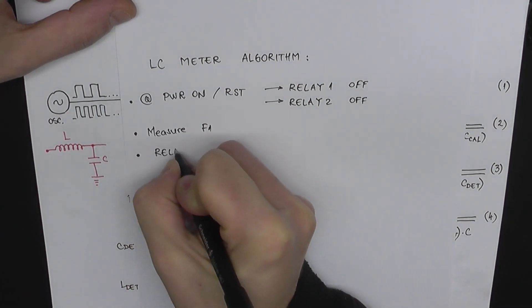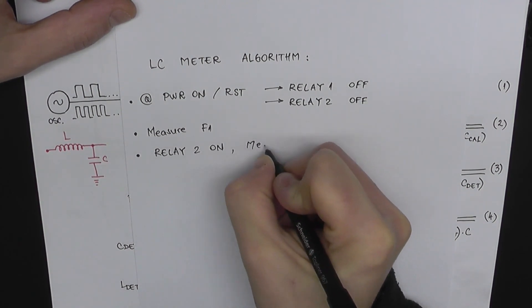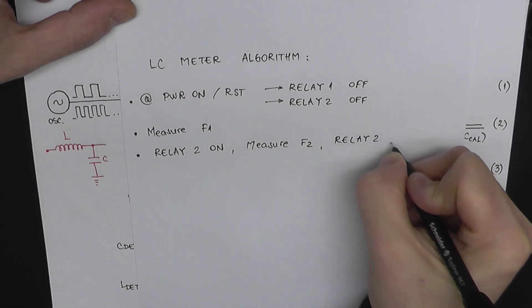Step 3: We switch on relay 2, which will connect the calibration capacitor to the oscillating circuit, and then we measure the frequency again, and then we switch relay 2 off.